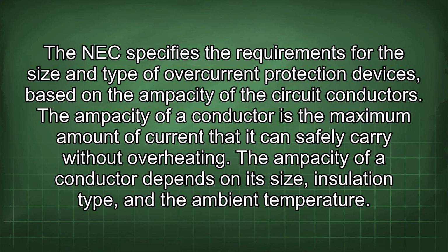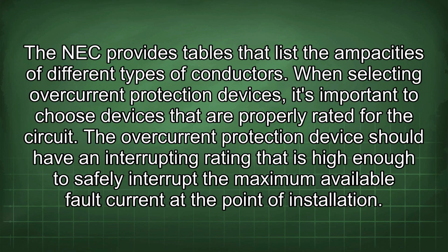The NEC specifies the requirements for the size and type of overcurrent protection devices based on the ampacity of the circuit conductors. The ampacity of a conductor is the maximum amount of current that it can safely carry without overheating. The ampacity of a conductor depends on its size, insulation type, and the ambient temperature. The NEC provides tables that list the ampacities of different types of conductors. When selecting overcurrent protection devices, it's important to choose devices that are properly rated for the circuit. The overcurrent protection device should have an interrupting rating that is high enough to safely interrupt the maximum available fault current at the point of installation.